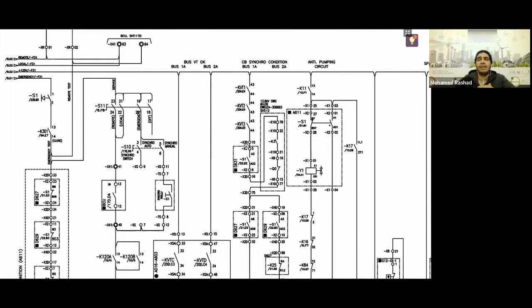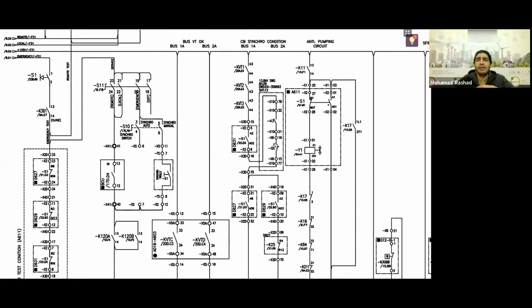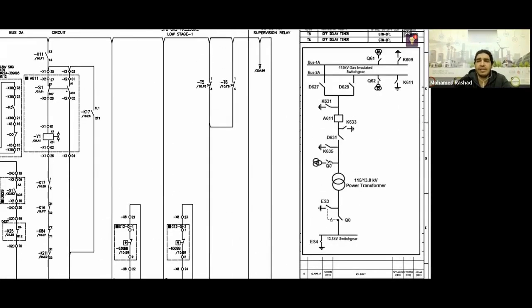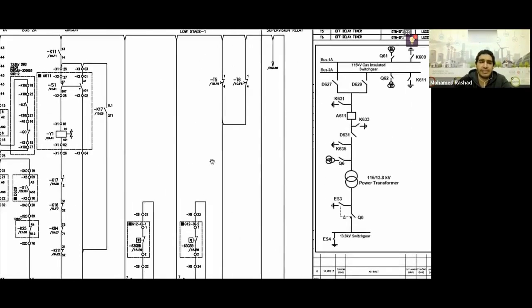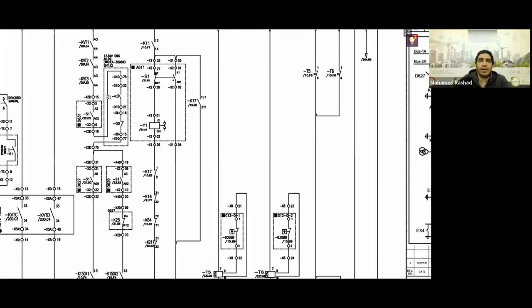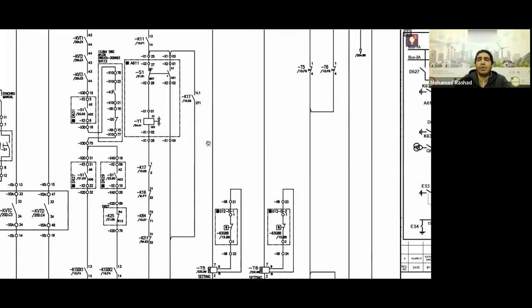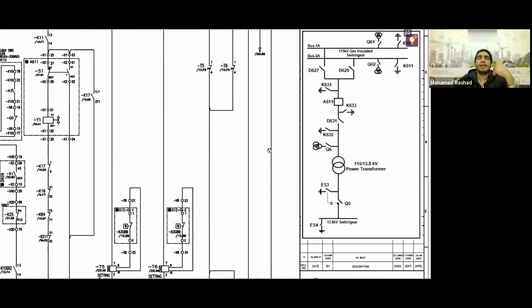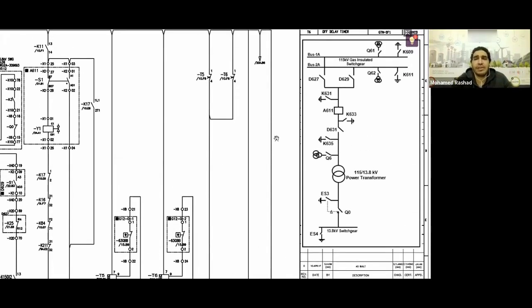What about my VT? Great. Then I move to D631, which is the line disconnector that should be closed. Here, the line disconnector is closed. Now, who is this part below? This part, engineers, is now telling you that you are closing in the service position. In the service position, you told me the disconnectors from before are closed along with the one after, right? But since you are dealing with a transformer, what are the conditions for closing the transformer? They are that we always close the high voltage side first, then we close the load side.